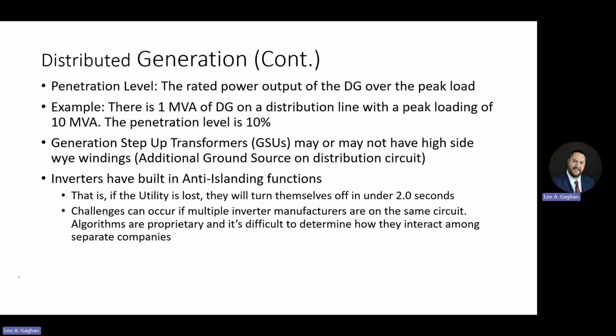Generator step-up transformers, commonly called GSUs, may or may not have high side windings, which would be an additional ground source in the distribution circuit. That can have certain impacts. And then one major consideration, especially in our protection world, is knowing that inverters have built-in anti-islanding functions, meaning that they usually can't operate when they become disconnected from the grid. That is, when the utility is lost, they usually will turn themselves off in under 2 seconds.